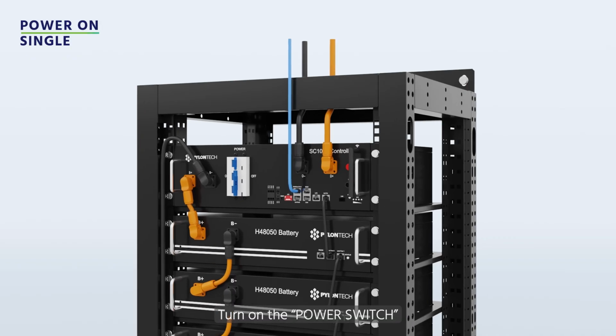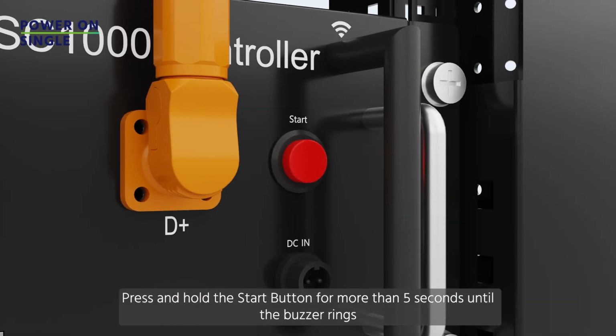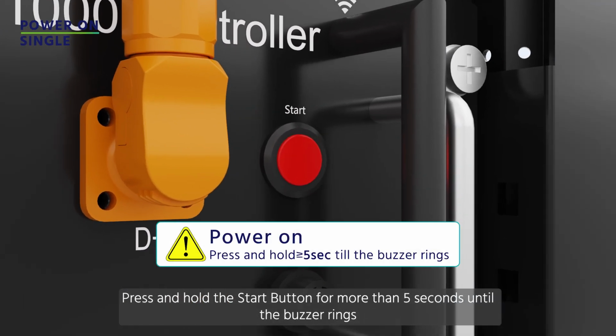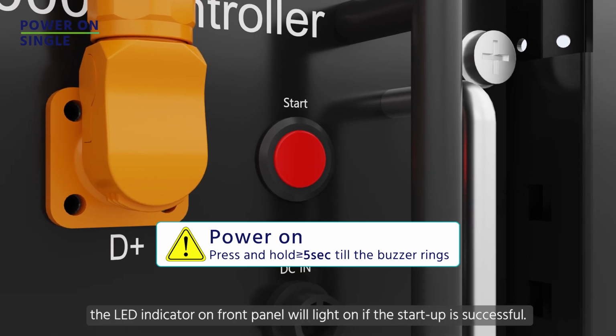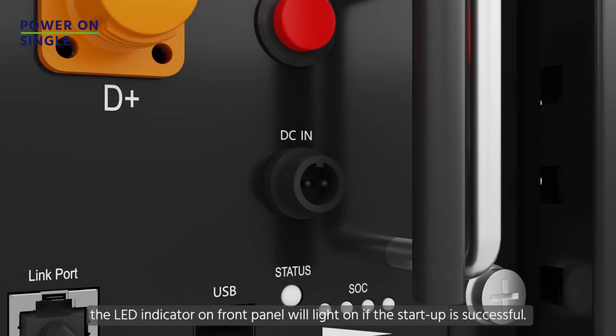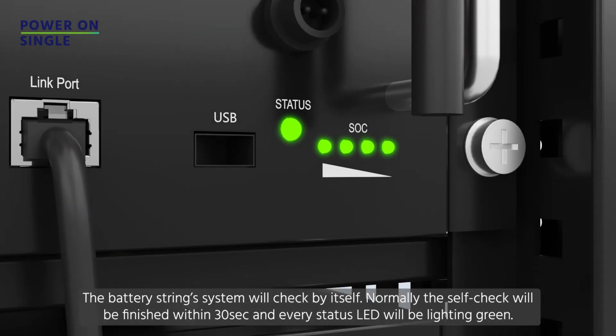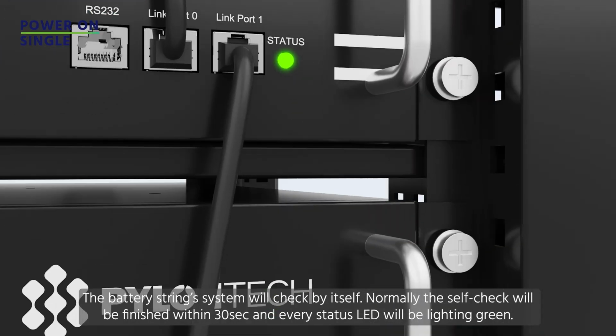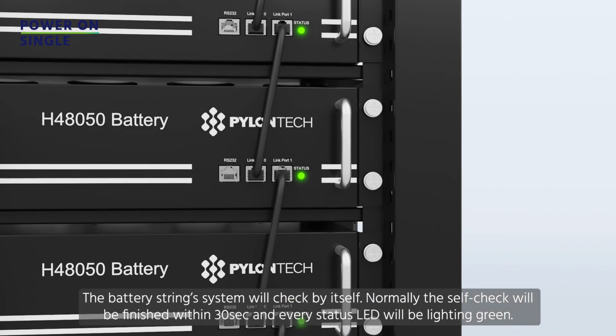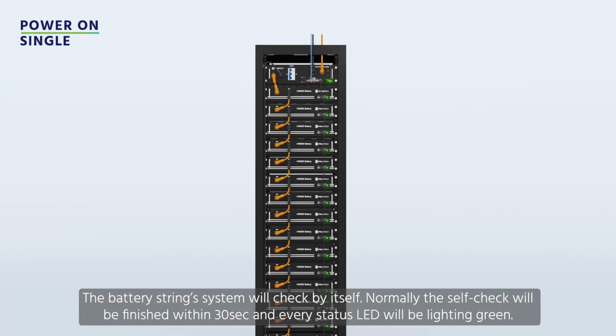Turn on the power switch. Press and hold the start button for more than 5 seconds until the buzzer rings. The LED indicator on the front panel will light on if the startup is successful. The battery string system will check itself. Normally the self-check will be finished within 30 seconds and every status LED will be lighting green.